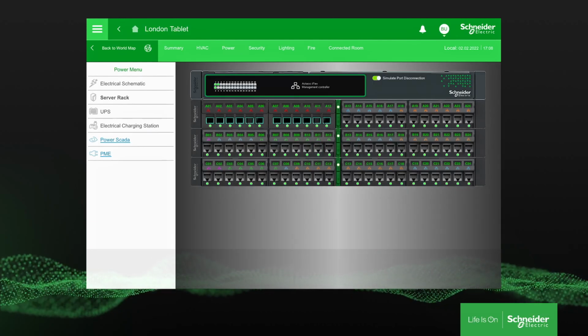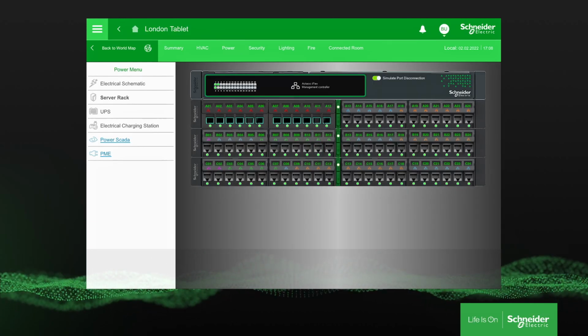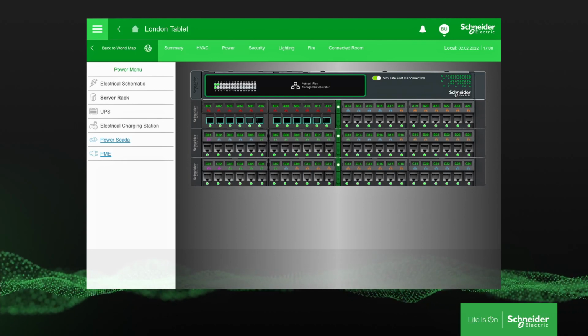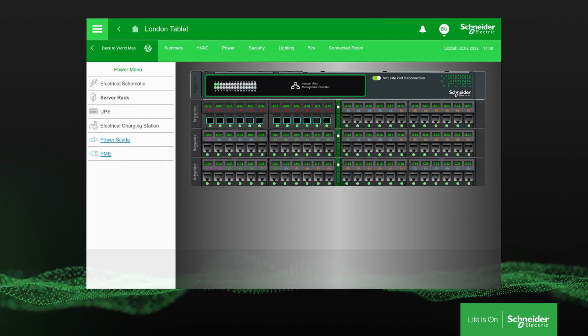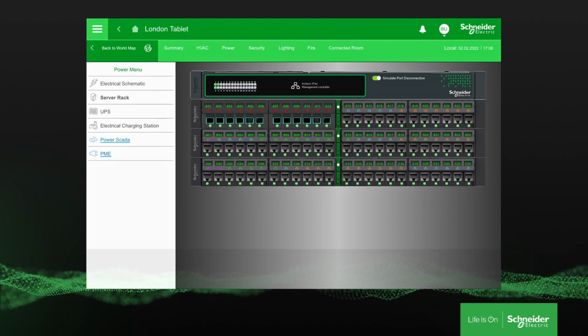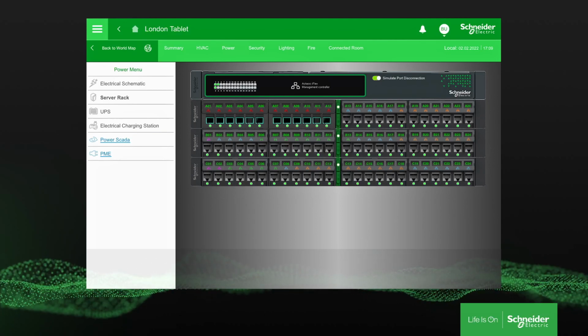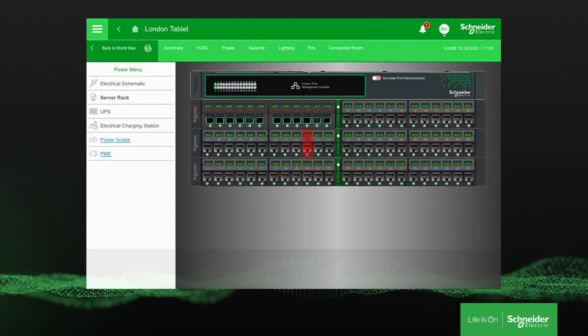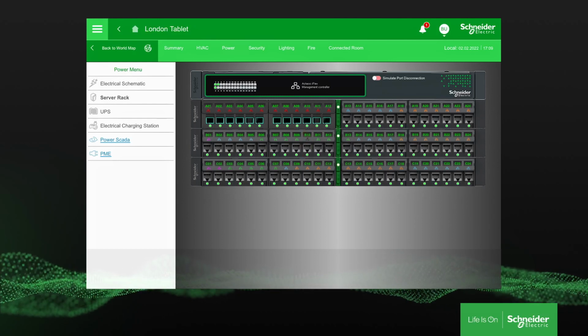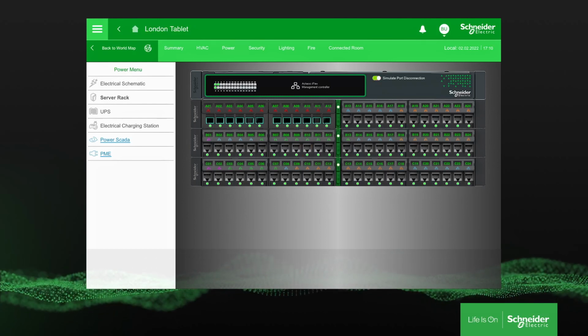I can also check that actual patch panel to see what is connected to what end and even to see if any of the connections have been broken. If any of the connections have been broken, I get an indicator on the panel with a flashing indication at the port. So everything looks good here.